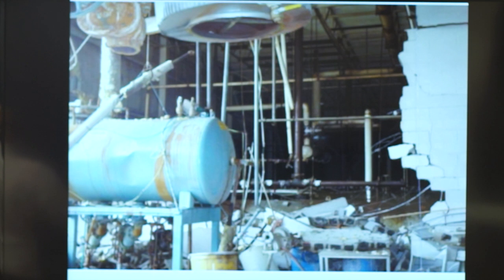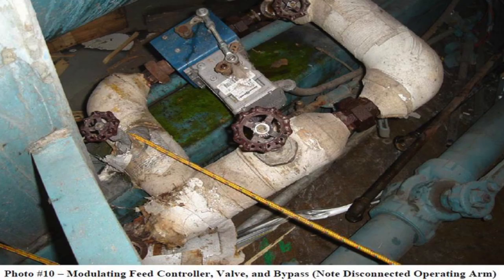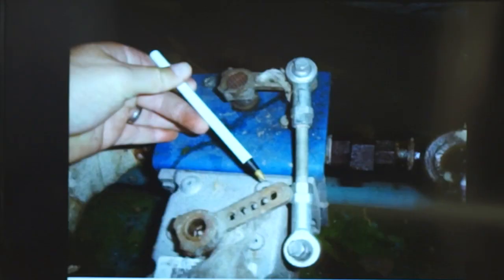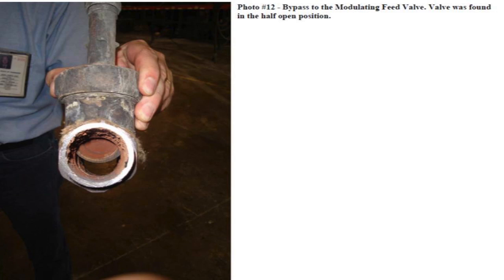The low water cutoff works like a float mechanism, like the one on the back of your toilet — McDonnell & Miller is one major manufacturer. The boiler was flooding, getting too much water. So the operators decided to fix the problem by going to the feed water valve with the Honeywell motor on it and disconnecting the linkage from the valve, partially opening or closing it manually.